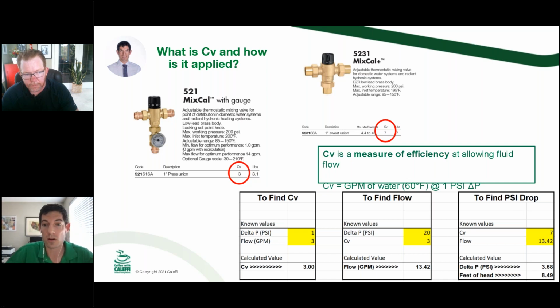So those are a couple things that we look at when we size a valve, is that maximum flow number that we need. If it is 13.42, we can kind of easily rule out that smaller valve. It's not going to be able to keep up without losing too much pressure. Yeah, I think, again, this is another one of those takeaways: just because you've used a 1-inch valve in the past doesn't mean that this other branded 1-inch valve is going to operate the same.